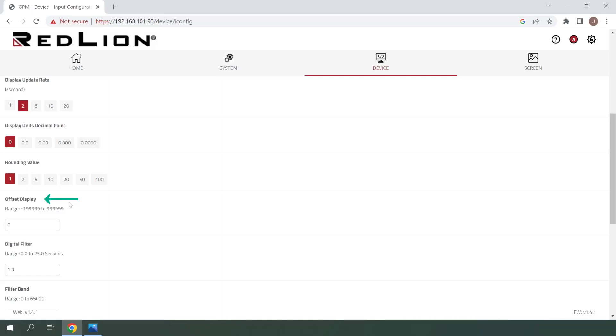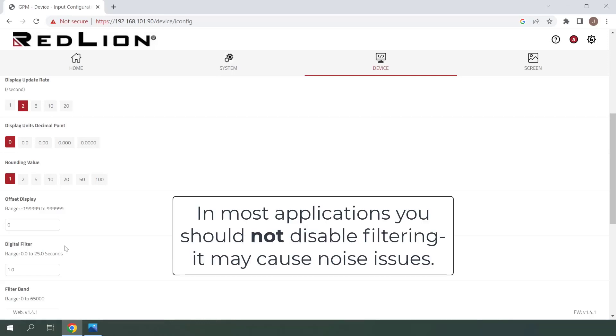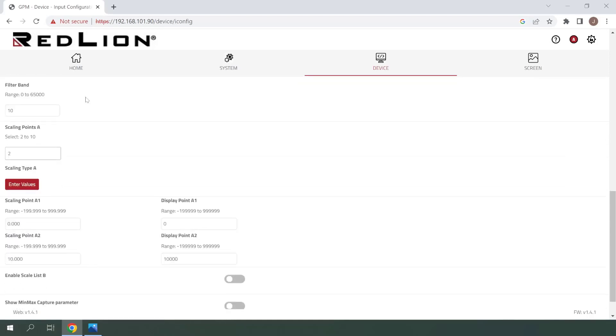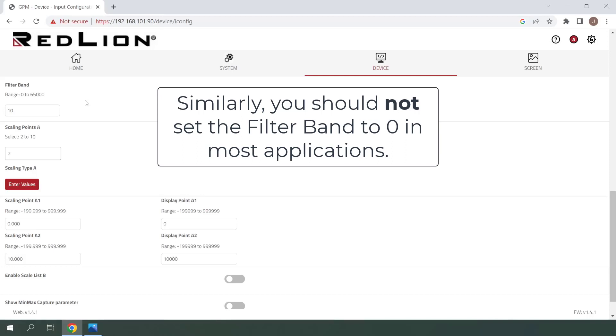In the offset display field, we can enter an offset value which would be added to the absolute value to create the relative value. I'll be leaving this at 0 as no offset will be needed here. Next, we have the digital filter which is designed to steady the input display reading. A value of 0 disables filtering, which I'll be doing for this demonstration. Here we have filter band — when input signal variation exceeds the input filter band value, the digital filter disengages. I'll change this to 0 since we're not using a digital filter.